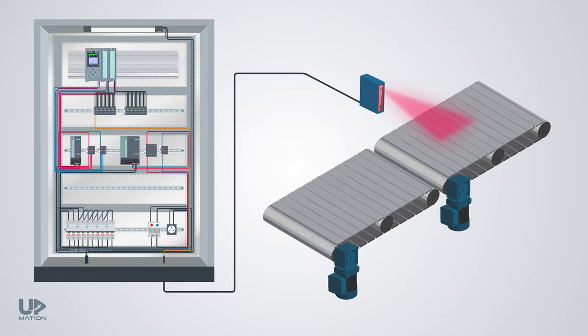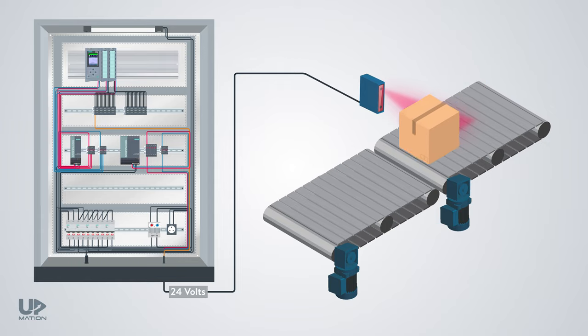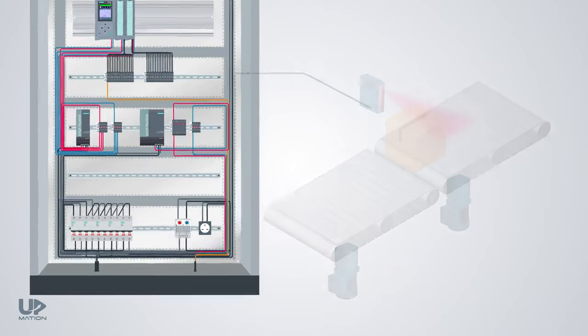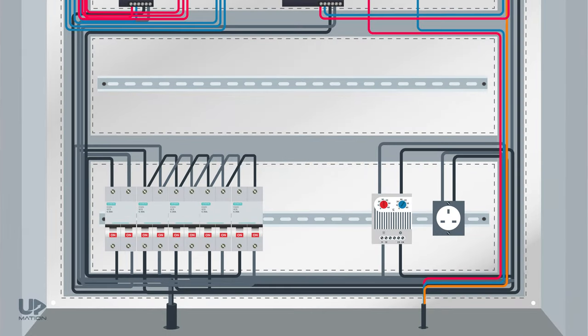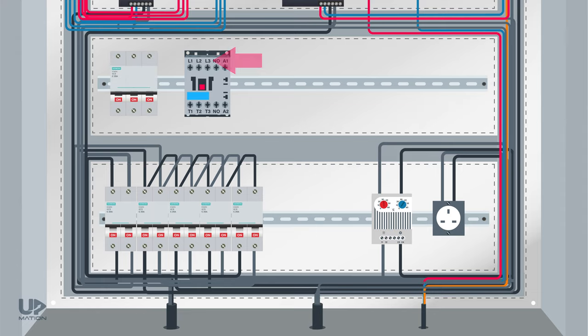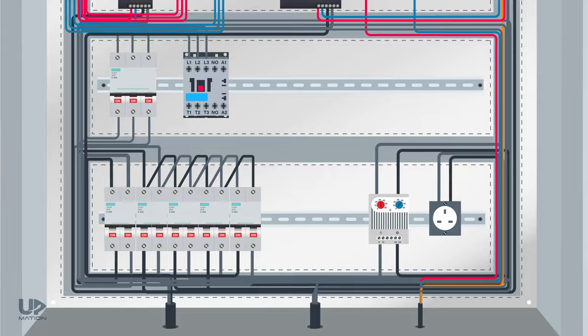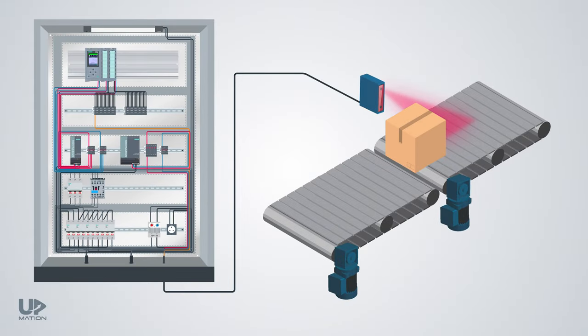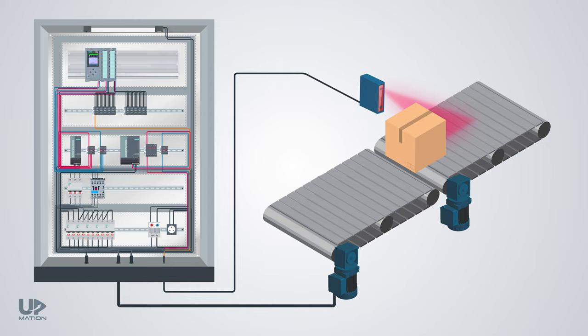After this sensor informs the PLC about the presence of the box, the PLC should command the next conveyor's three-phase motor to start turning. To do so, we should add a contactor to our control panel. Connect three-phase power to its input and lay a cable between the contactor and the motor connection box. Actually, when we have three-phase power within our electrical control panel, the arrangement of the panel would be somehow different from what you see here. But let's take it easy and move on for now.